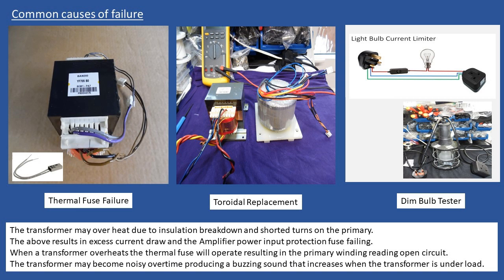Now, on the left hand side, what you can see here is an EI type transformer. So this is one of the laminated transformers, and this has been removed, so it's a real transformer that has failed. And the failure can be in multiple ways. Alright, so I'm going to talk about this one first off, and I mentioned this at the beginning of this tutorial. It is not uncommon for these transformers to have what we call a thermal fuse.